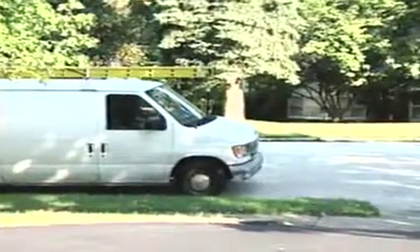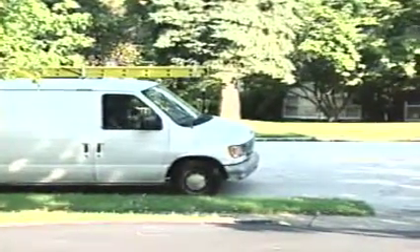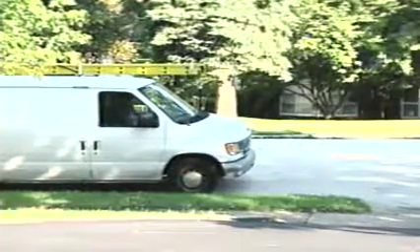Be wary of customers who try to do your diagnosis for you. Make sure they describe symptoms instead of telling you how to correct the problem. If you have to, probe a little. So what seems to be your problem? Well, we have no cold air coming from our registers. Okay, did you happen to check the circuit breaker? No, I figured it wasn't that. What makes you think that? Because the blower in the basement was working and the unit outside was working as well. The condensing unit? Yes, that's it. Okay, why don't I take a look at the system?